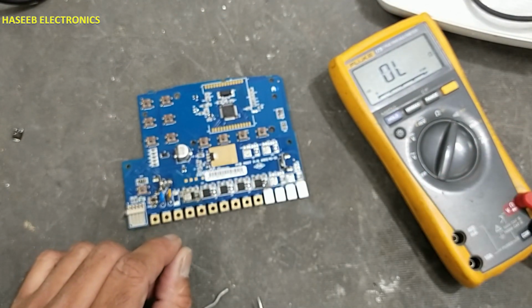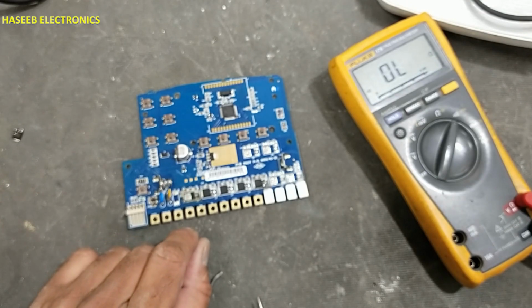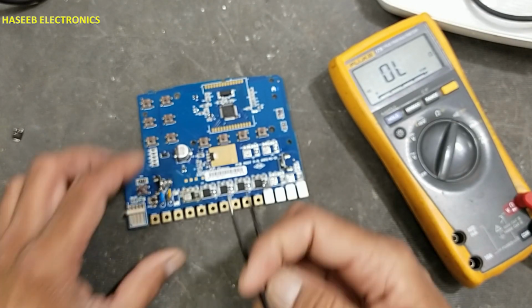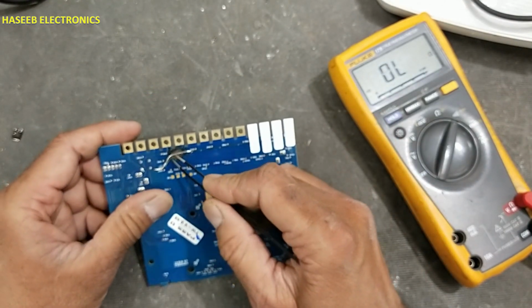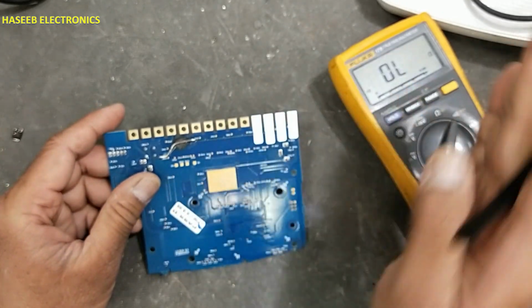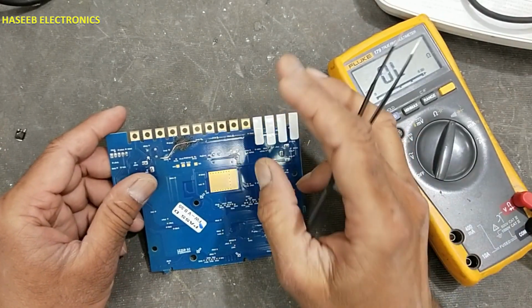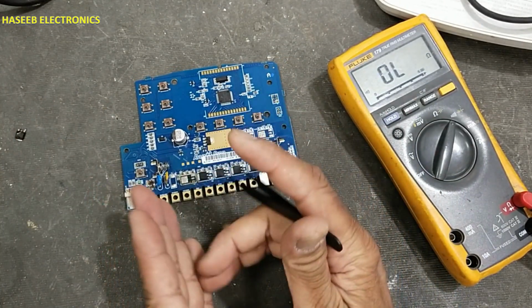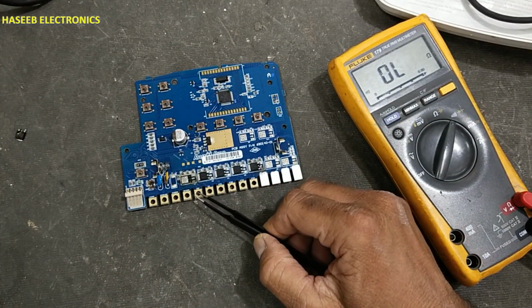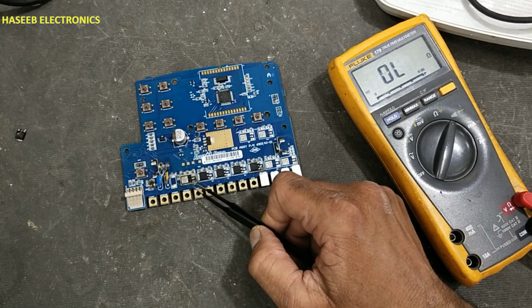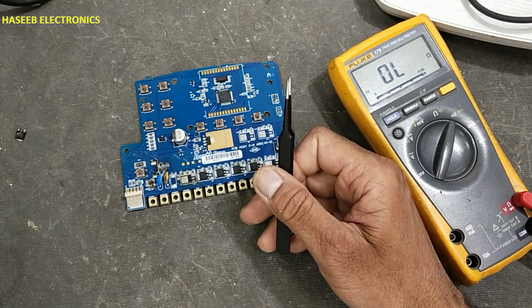Its transformer is very small. It is just only 0.68 ampere. That cannot provide so heavy a spark. In this situation, the transformer must be damaged. But I think there is some mistake or some unnecessary electric reached here, or might be some bad connection.